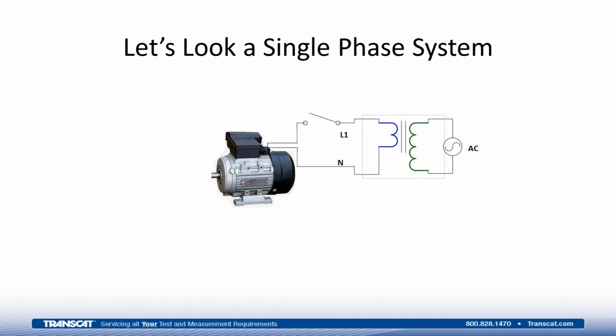I would then attach a current probe anywhere along that L1 line, wrapping it around the conductor. It could be attached anywhere from the transformer all the way to directly at the motor itself, and that would monitor the current flowing into that motor. Using the information from the current monitoring as well as the voltage that we picked up from the two leads, I would be able to calculate wattage of that motor. Accumulating that over time would give me the watt hours, that is the energy that that motor is drawing.